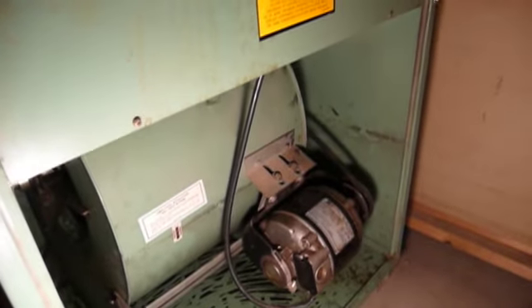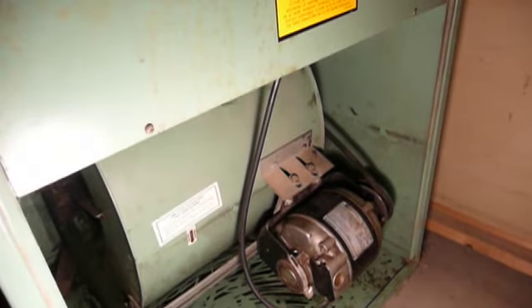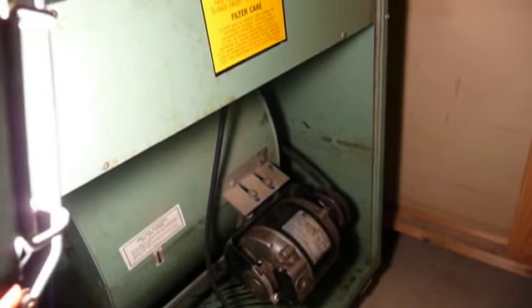Let's go in the house and look at a few things. Here's the inside of the furnace — this is an old Singer furnace. I don't know exactly how old it is, but back when I was a kid I was born and raised in this house, and this thing is at least as old as I am. I would assume that motor is probably original to the furnace. Everything seemed to be working okay, except the fan was not approaching full speed and there was definitely a rhythmic thumping noise.